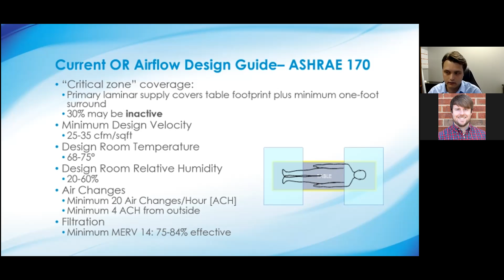Now, recently, in just the past few weeks, ASHRAE 170 actually updated their code for 2021 to say that the minimum filtration into an OR must be MERV 16, so 95% effective at the 0.3 micron size, which is a step in the right direction. Still not HEPA, still not 100%, but in rooms that have orthopedic procedures, transplants, neurosurgery, they have a specific list of critical surgeries, those rooms must have HEPA filters in the diffusers per the new updated code. So they're moving in the right direction. But now the question is, even if you have HEPA filters in the ceiling, how much is a design like this doing to protect the patient?